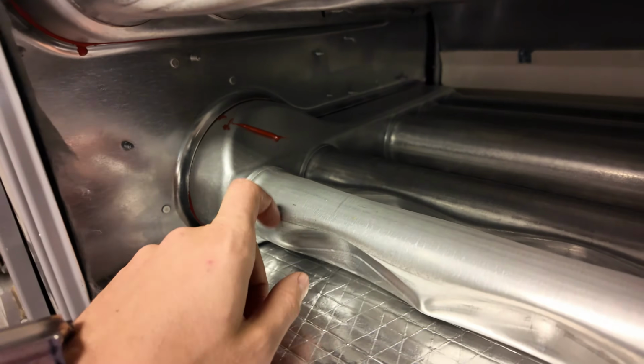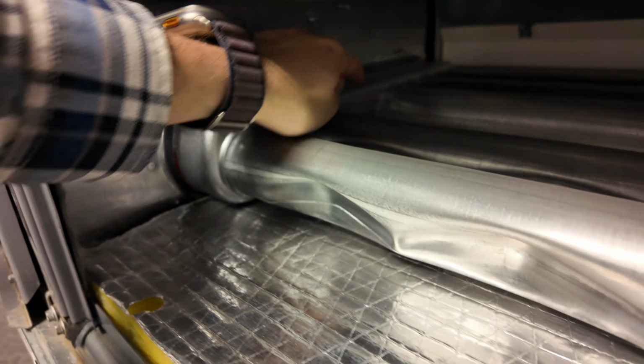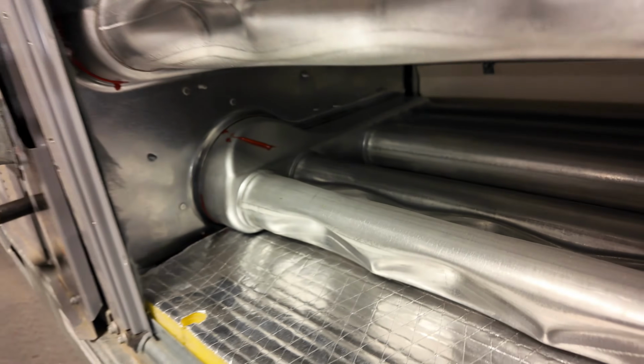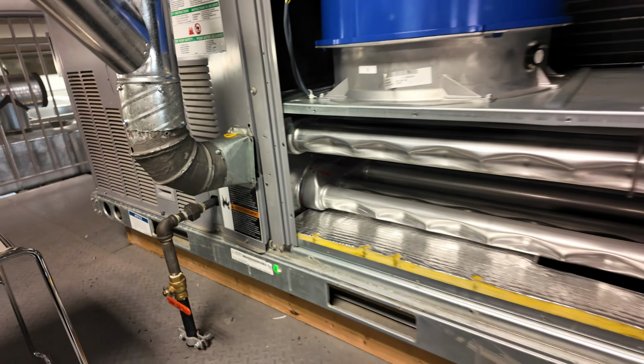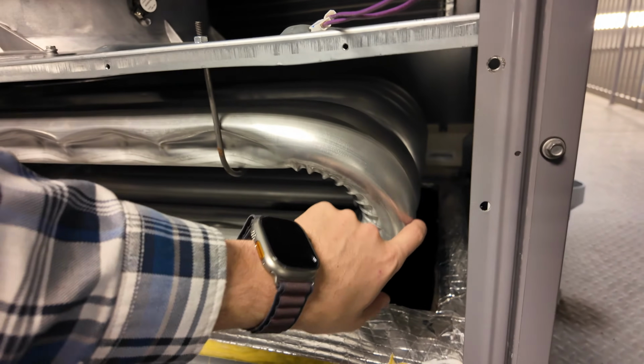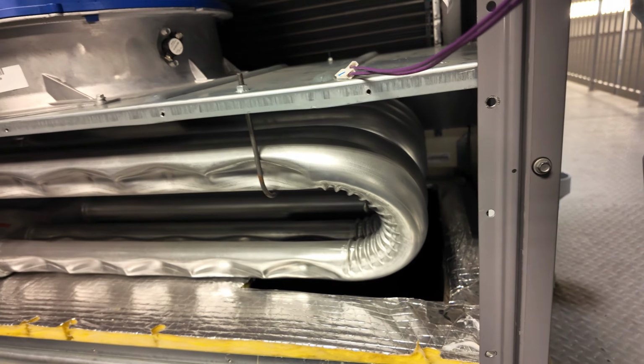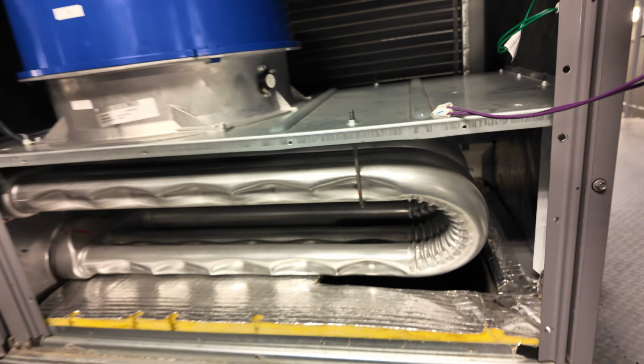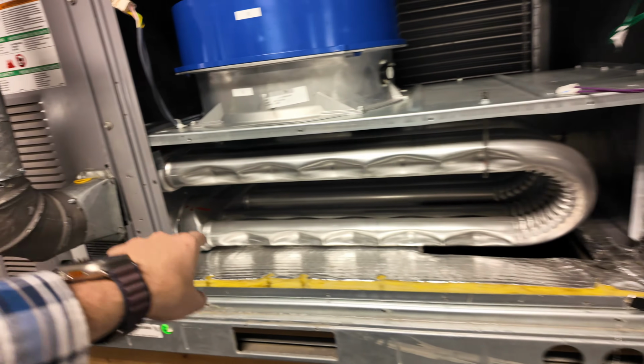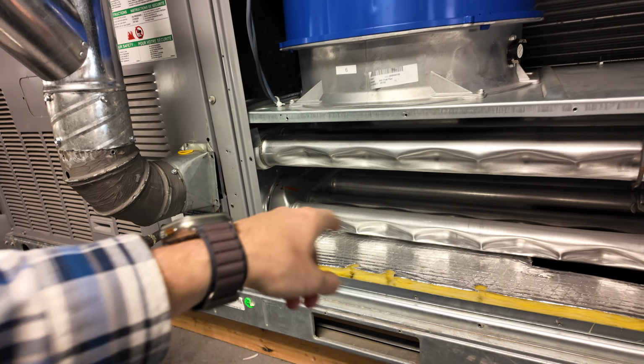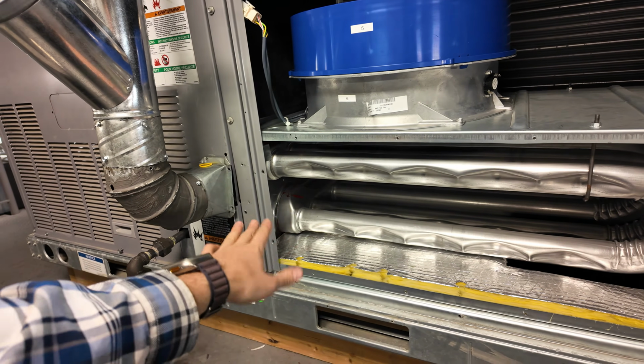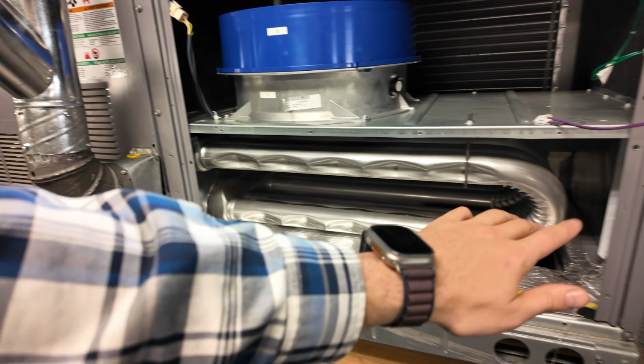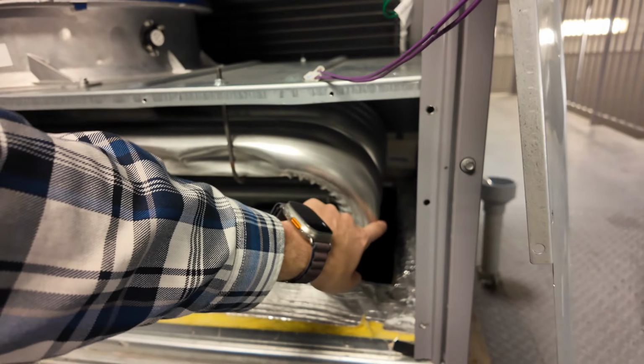But you would not be shocked if you found a crack anywhere here, any time of the year in a heat exchanger for Carrier. I have seen them crack on the U-bend. That's most common on most units, but actually not on Carrier. The Carrier are usually right there in that front seam. So if you're looking for cracks on heat exchangers, that's your most common spot. And then second is over here.